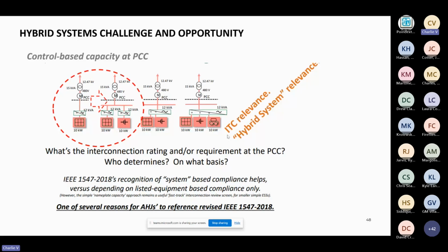Basically, control-based project power ratings — you open up the potential to use that, which is really at the front end of adoption. Not all folks adopting 1547-2018 are taking advantage of the fact that 2018 really clarifies that you can do a system rating and system compliance at the point of common coupling, and it doesn't have to be the aggregate rating of each individual nameplated unit. You don't necessarily have to push the compliance down if you truly have a compliant system interface with the appropriate isolating capability.